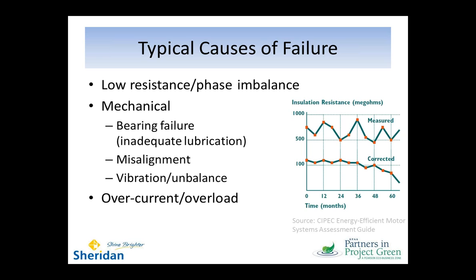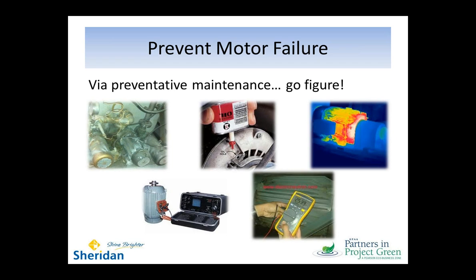This graph is showing a case where they've measured the insulation resistance every 6 months over a period of about 5 years. You can see it holds quite well for about 4 years, and then in about the 5th year it begins to decline, and that's an indication for them at this point. They probably need to consider replacement of the motor or a rewind or something at that point. So they've essentially established a predictive replacement that they have to do.